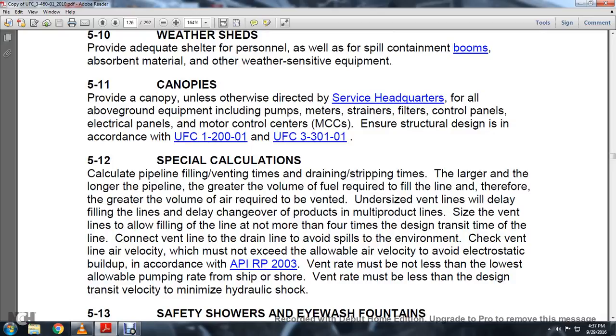512 special calculations. Calculate pipeline filling and venting time and the drain and stripping time. The larger and the longer the pipeline, the greater the volume of fuel required to fill the line, and therefore the greater the volume of air required to be vented. Undersized vent lines will delay filling the lines and delay the output of the products from the product lines.